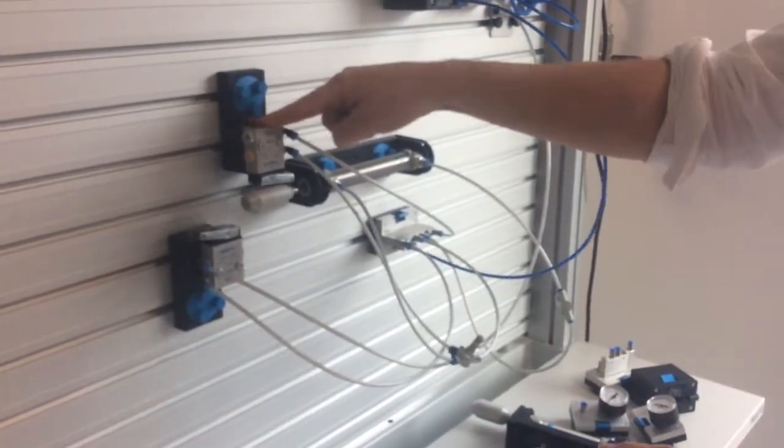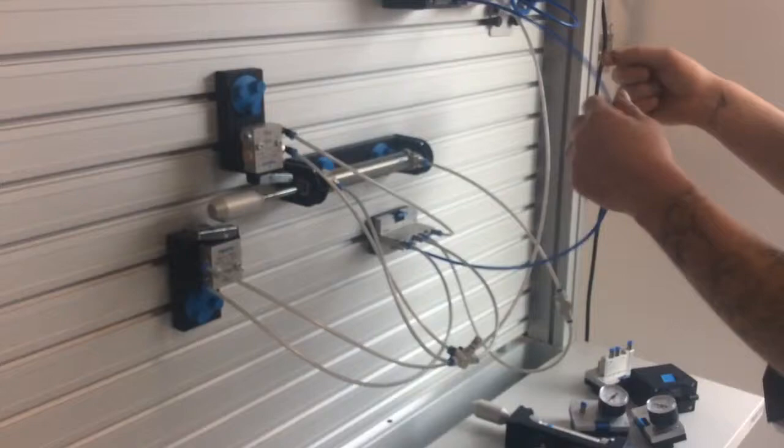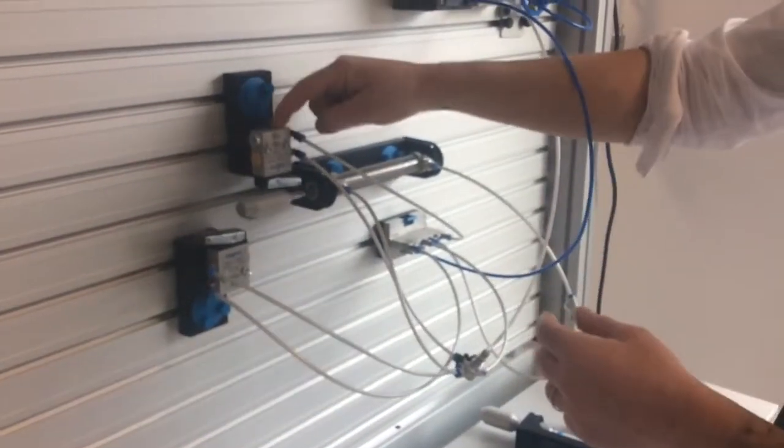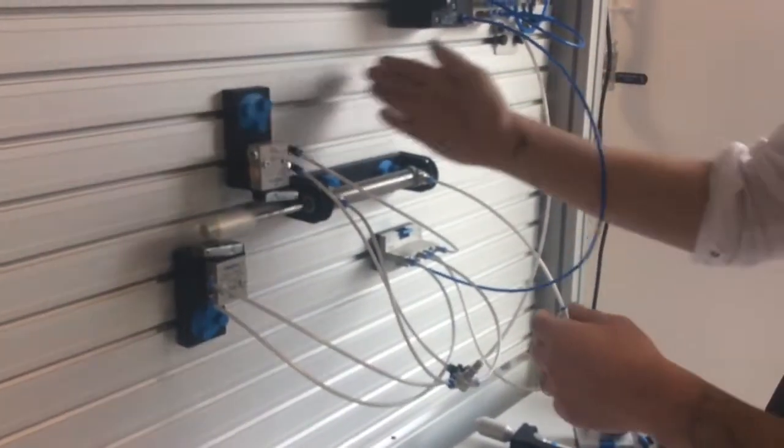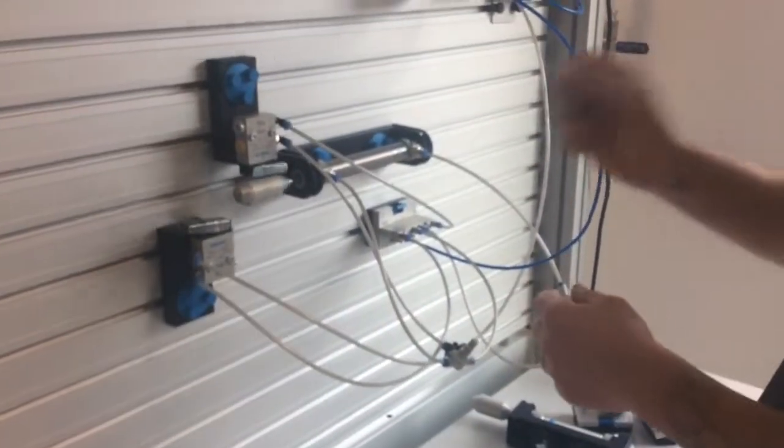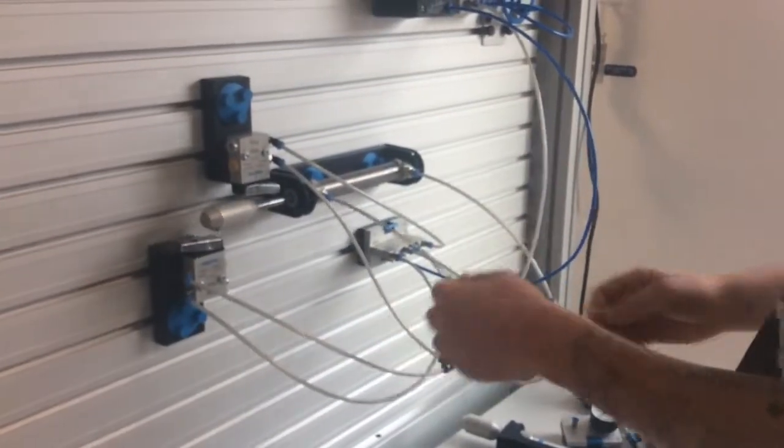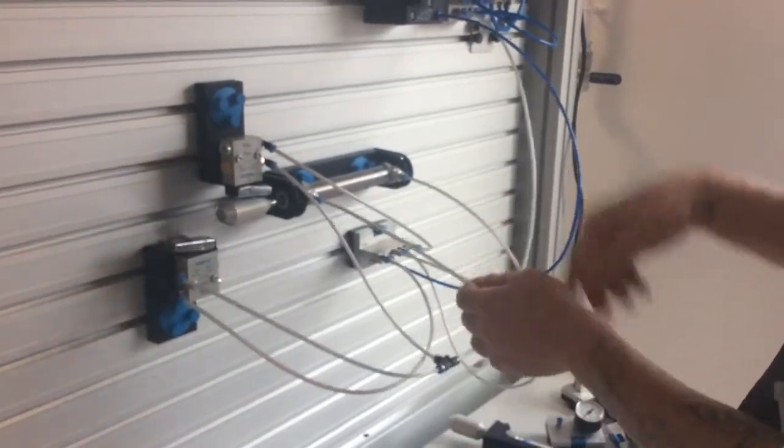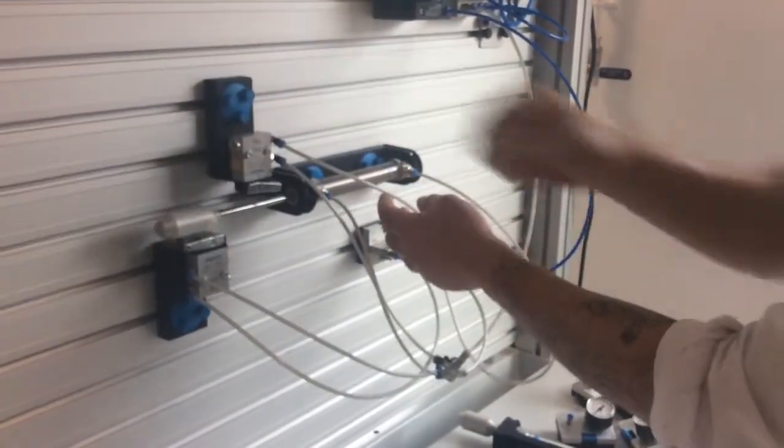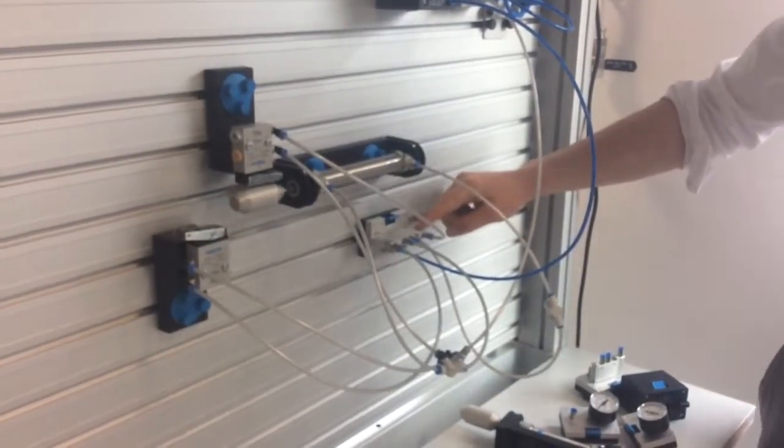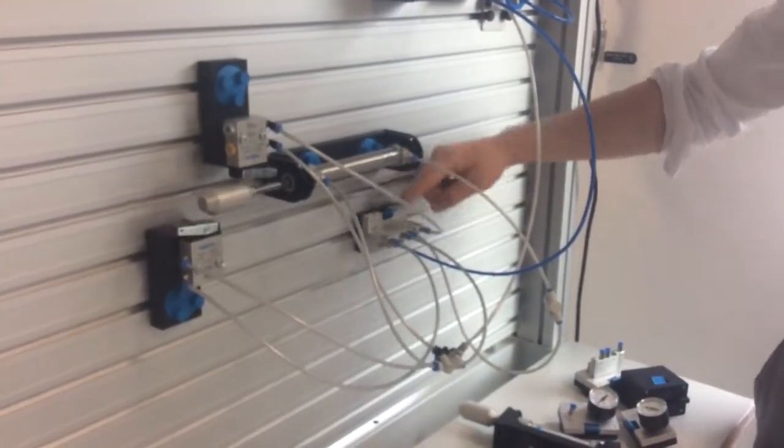Likewise, the same is happening on our right-hand switch. So when the right-hand limit switch, the in-limit switch is made, our pressurized air through our T-piece, through port 1, is allowed to flow through into the right-hand pilot.